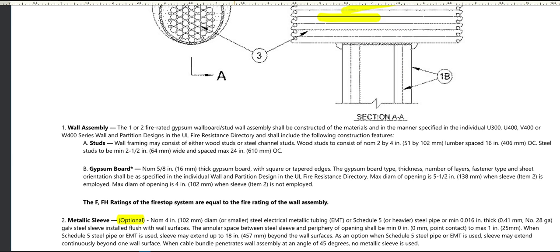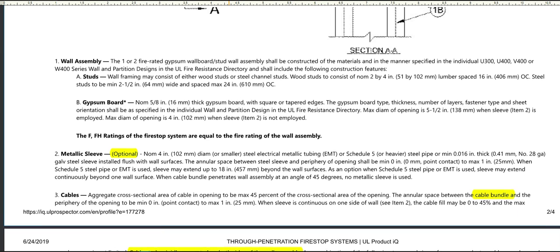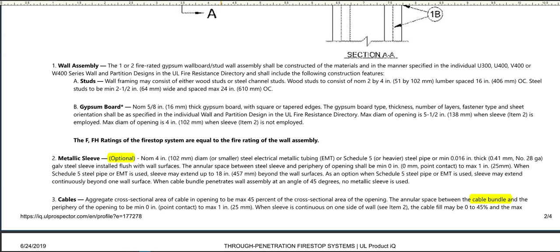It starts to talk about the wall assembly, and this is often overlooked — the construction of the wall itself. Even if you're not the framing inspector or fire marshal, we still need to verify that the most stringent design is being followed. This listing says any one or two hour rated gypsum wall stud assemblies are permitted, and it goes further to say you can use hundreds of different types of wall assemblies provided by UL, each with their own test standard and installation system.